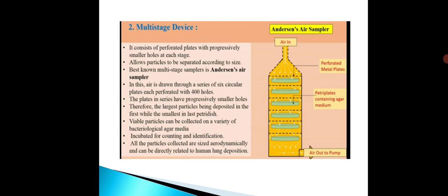The second type is the multi-stage device. The sampler used here is Anderson's air sampler. This device consists of perforated plates with progressively smaller holes at each stage, which allows particles to be separated according to size. In Anderson's air sampler, air is drawn through a series of six circular plates, each perforated with 400 holes. The plates in the series have progressively smaller holes, so the largest particles are deposited on the first plate while the smallest are deposited on the last petri plate.